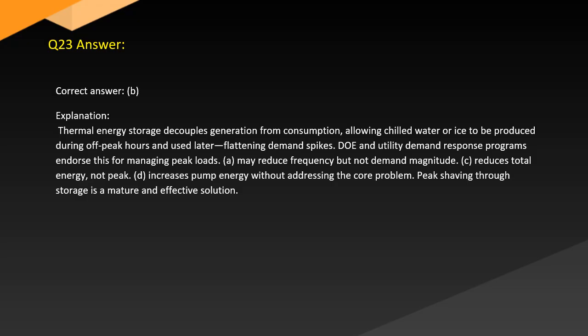Answer. Correct answer. B. Explanation. Thermal energy storage decouples generation from consumption, allowing chilled water or ice to be produced during off-peak hours and used later, flattening demand spikes. DOE and utility demand response programs endorse this for managing peak loads. A. May reduce frequency but not demand magnitude. C. Reduces total energy, not peak. D. Increases pump energy without addressing the core problem. Peak shaving through storage is a mature and effective solution.